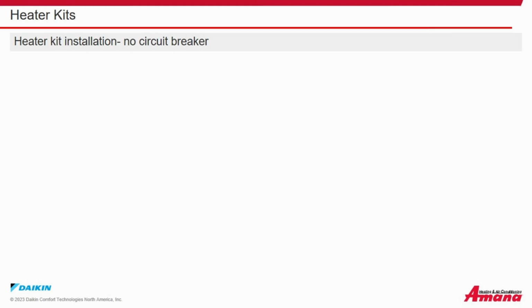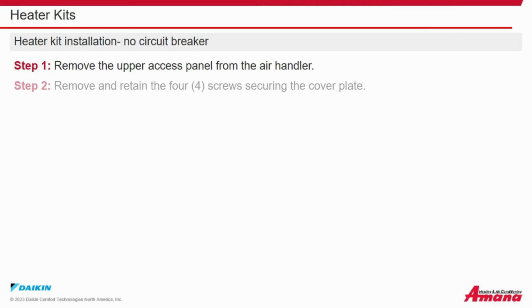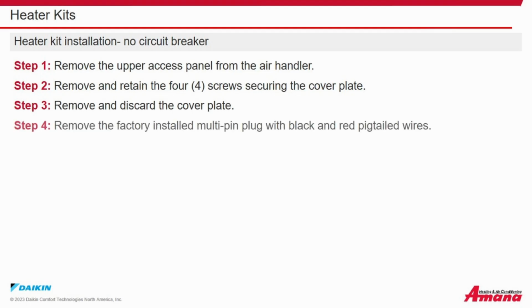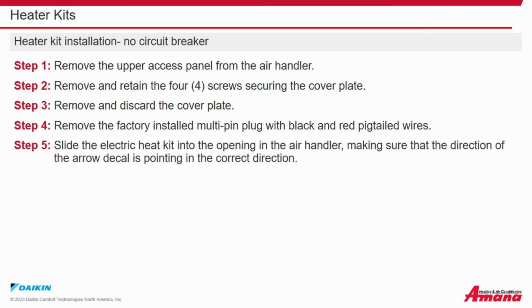Heater kit installation with no circuit breaker. Step 1. Remove the upper access panel from the air handler. Step 2. Remove and keep the 4 screws securing the cover plate. Step 3. Remove and discard the cover plate. Step 4. Remove the factory-installed multi-pin plug with the black and red pigtailed wires. Step 5. Slide the electric heat kit into the opening in the air handler. Make sure that the direction of the arrow decal is pointing in the direction of the airflow.